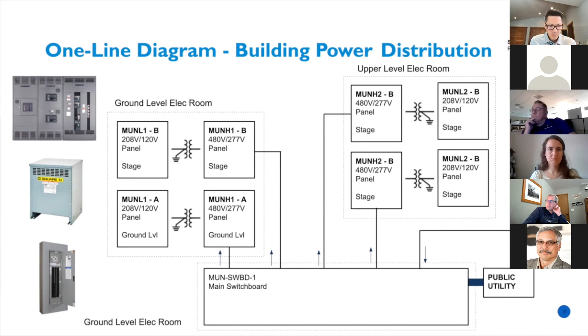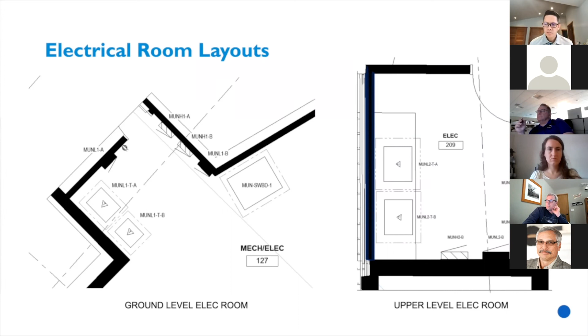For the 2 electrical rooms, we designed and laid out the equipment needed to power the building. We referred to the code found in the National Electric Codebook to lay out the panel boards and switchboards accordingly to meet all the safety requirements, which means having no equipment that will block the passageways. We will have a bigger electrical room located on the ground floor to service the ground floor spaces, and a smaller electrical room on the upper floor to service the upper floor spaces.